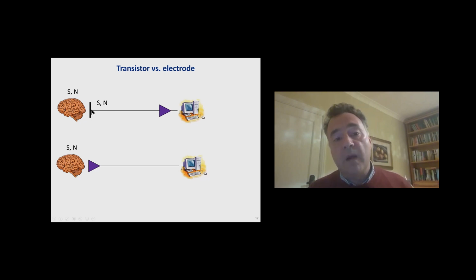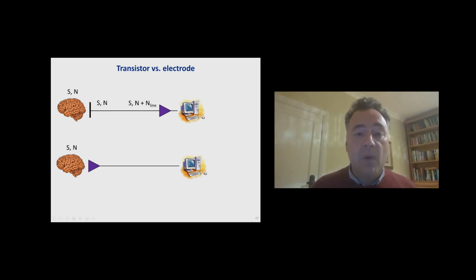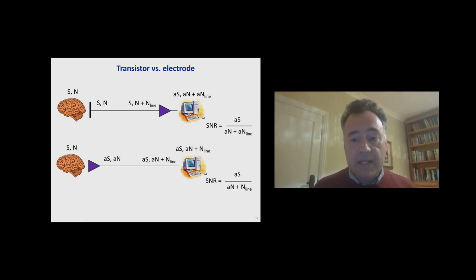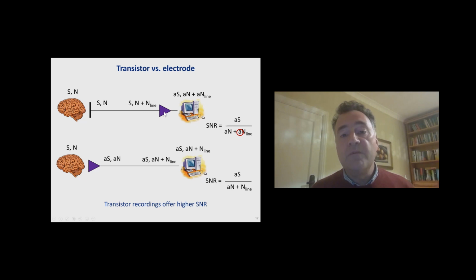Then you need to have your electrode connected with a wire to an amplifier and a recording system. And this cable acts as an antenna that picks up signals from cell towers, the lights in the room, the anesthesia equipment. So you end up having quite a lot of noise. When your amplifier amplifies this, it amplifies not only the signal, but also the noise. The argument goes that if you were to move your amplifier close to the source of signal, you would amplify signal and biological noise, but not any additional noise picked up on the line. So you'd end up with better performance, a better signal-to-noise ratio.